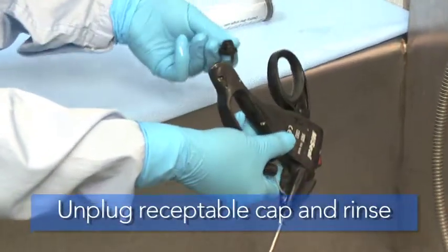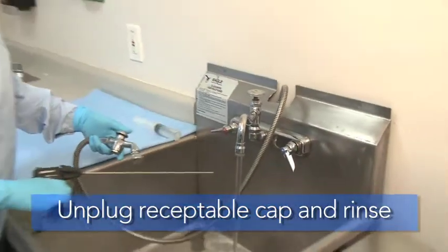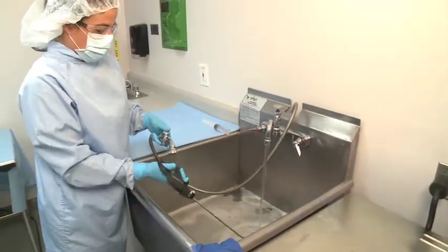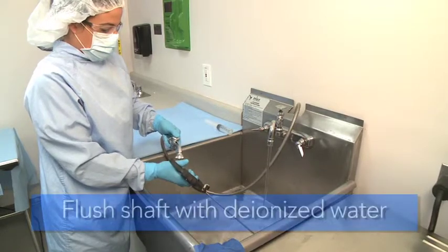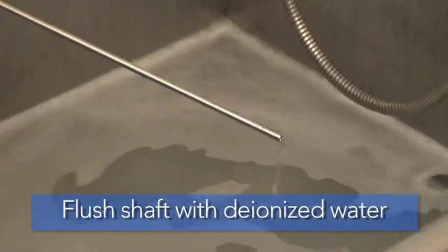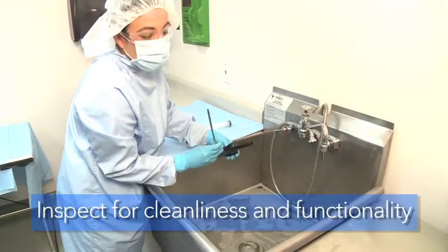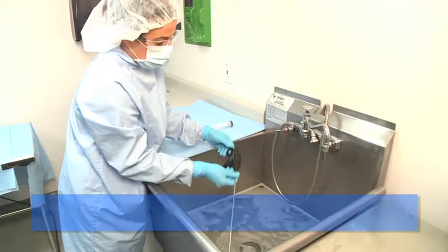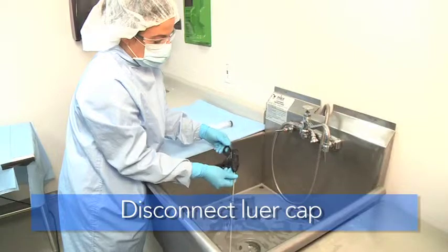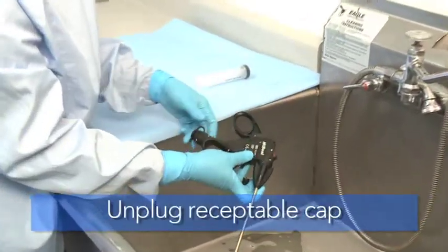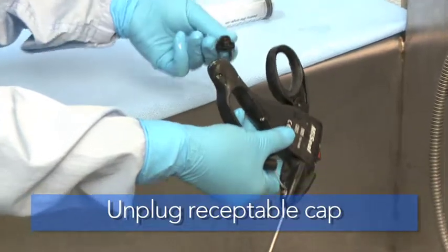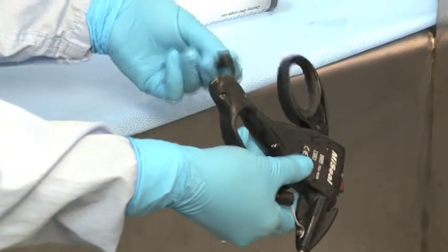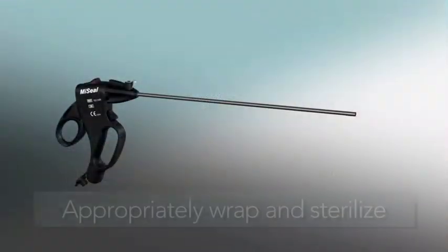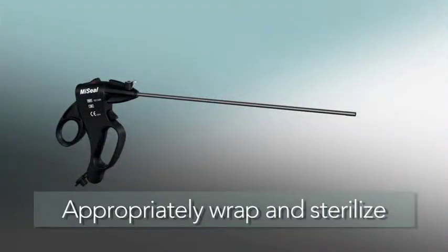Unplug the receptacle cap and rinse the entire device with deionized water for 1 minute. After the rinse, flush inside of the shaft 3 times with deionized water for a final rinse. Inspect the instrument for cleanliness and functionality. Before packaging for sterilization, make sure to disconnect the Luer cap from the flush port on the rotator knob and unplug the receptacle cap from the bottom of the handpiece. Prior to sterilization, ensure that the instrument has been thoroughly cleaned. Appropriately wrap and sterilize the device, following the protocol provided by the sterilizer manufacturer.